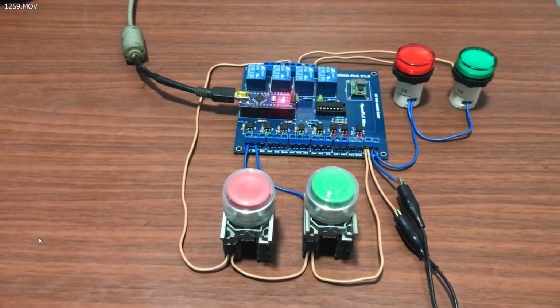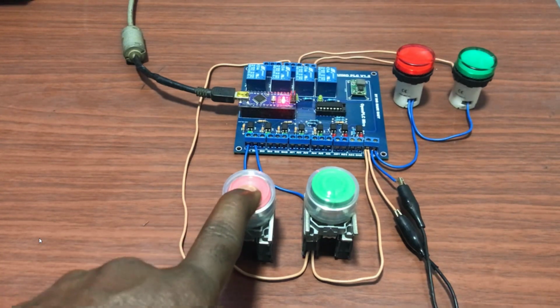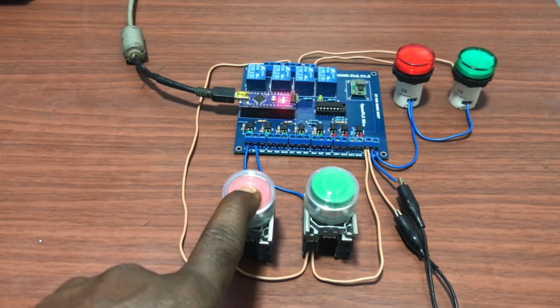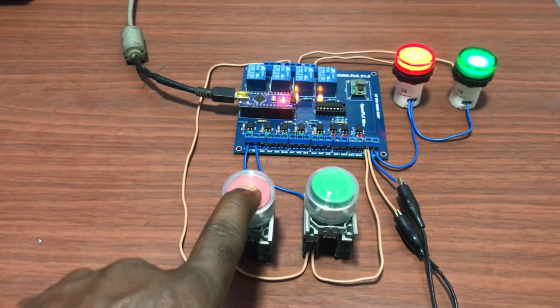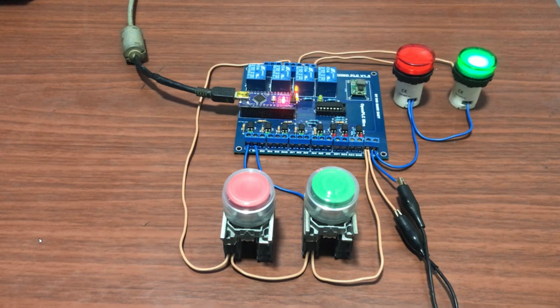Great, uploading done. So when I press on the first input, I need to hold on for 5 seconds. And we can see both outputs come on. When I release it, the red lamp goes off, but the green lamp remains on, which is output two, for 5 seconds, and then it is off.